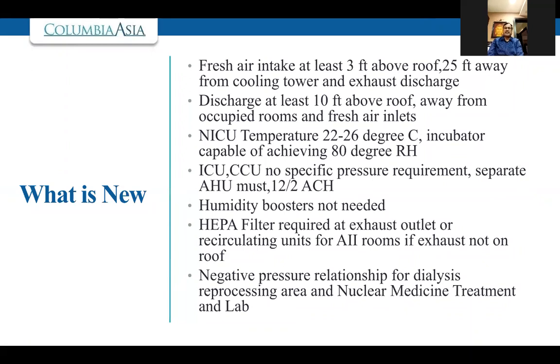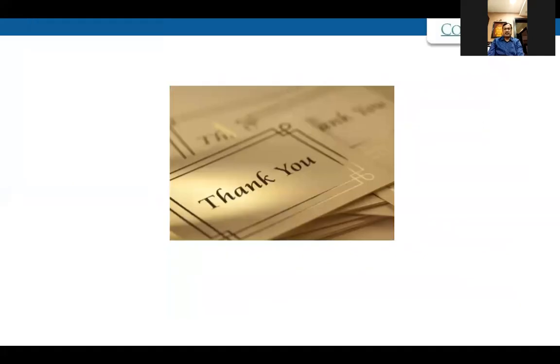Many of the multi-story buildings you must have seen, the isolation rooms are somewhere in the middle floors. So for them, if they discharge the air outside, it will again come back to the hospital. That's why there is a requirement of HEPA filters for such isolation rooms which are not exhausting directly onto the roof. Nuclear medicine lab as well as bronchoscopy also need to have a negative pressure relationship. These are some of the newer things which I have compiled for your benefit.